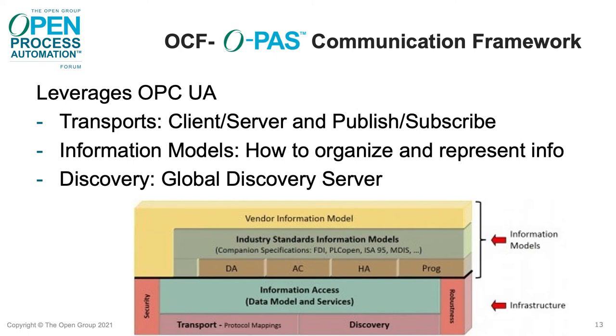The O-PAS communication framework leverages OPC UA, which provides client-server and publish-subscribe transports, and information models which describe how to organize and represent information. It also uses the GDS global discovery server to discover equipment, services, and data available, location of signals, and manage security credentials and authorization.